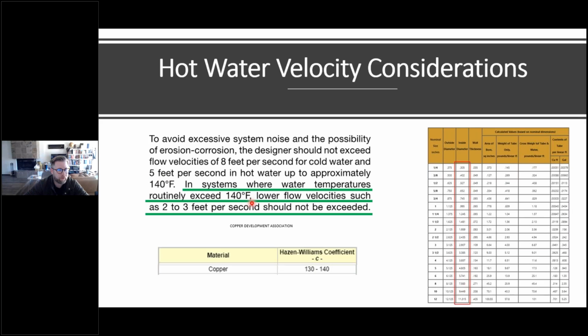For systems that utilize a temperature over 140 degrees, like if you're thinking 150 or 160 because of waterborne pathogens, if that's one of your strategies, you have to lower your velocity to 2 to 3 feet per second. Also, when you're calculating your velocity, do not use nominal pipe size, use the inner diameter. Otherwise you're either more likely than not overestimating or potentially underestimating your capacity in your system.